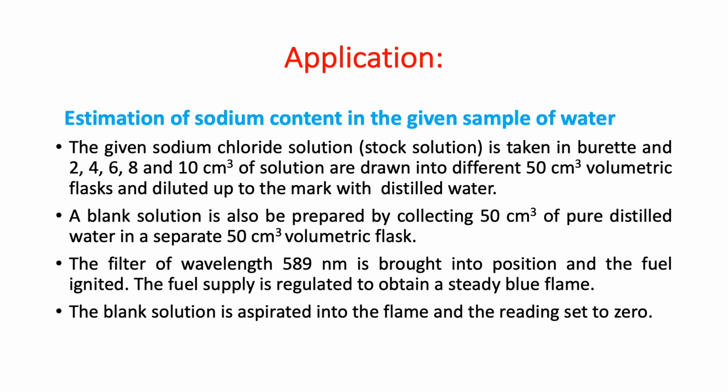This filter will allow light energy of only 589 nanometer. For each element you have separate filters, so in order to send that particular light to the detector, you have to set this 589 nanometer. Afterward you have to aspirate the blank solution, followed by the standard solutions and your test solution.